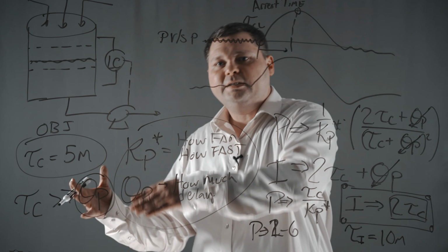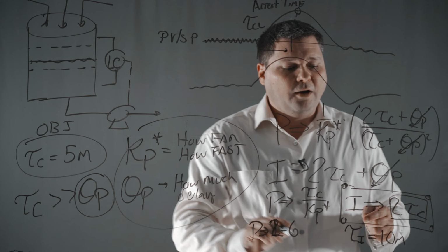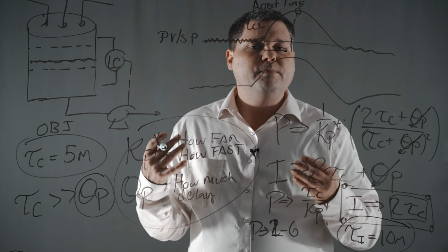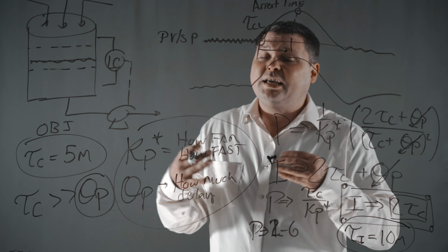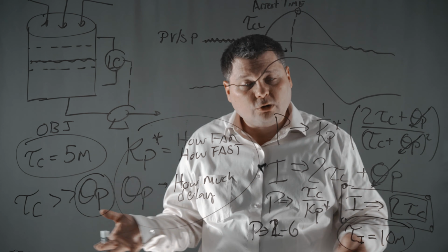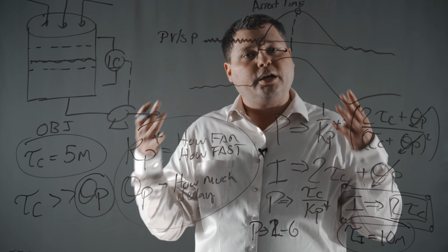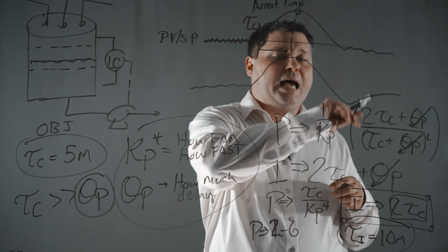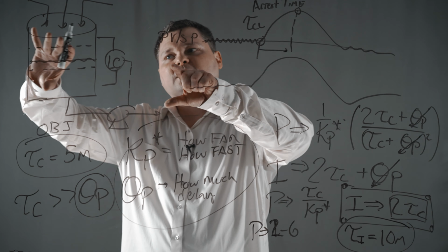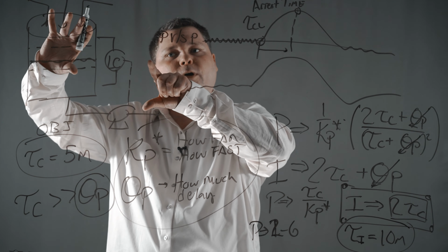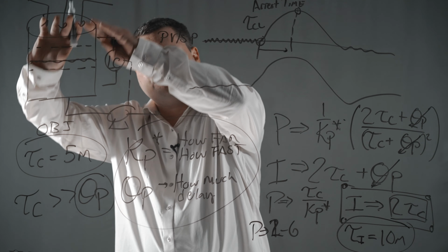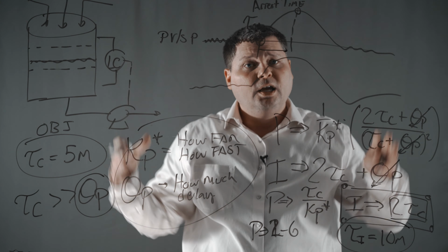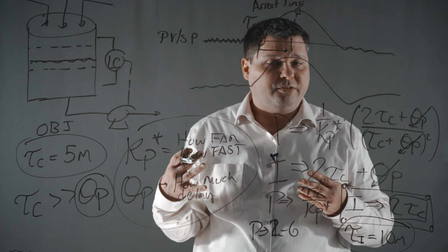Most level controllers tend to be cycling and oscillating, oftentimes because their reset time is much too fast. It'll be 1 minute, it'll be half a minute, when it should be like 10 or 12 minutes. Once we increase that reset time, slow down that integration, we're able to bump up the gain a little bit, get that level to balance out, to smooth out. Because these tanks tend to connect pieces of equipment, by tuning your level controllers, balancing them out, and getting them to be stable, you can start to decouple your processes and really start to improve the efficiency of your plants.